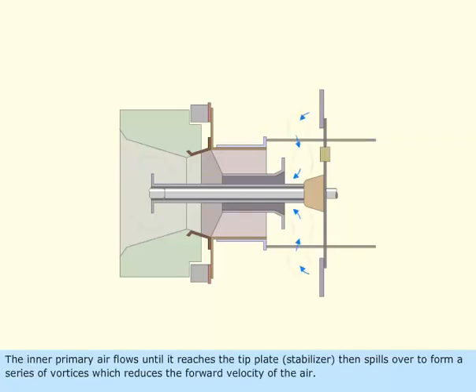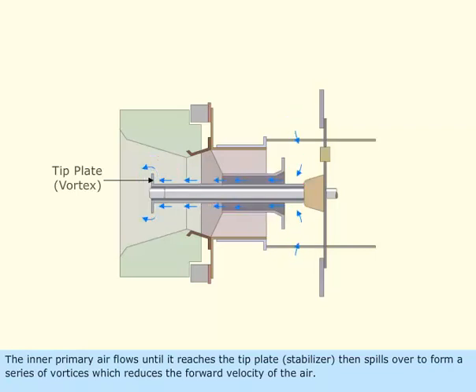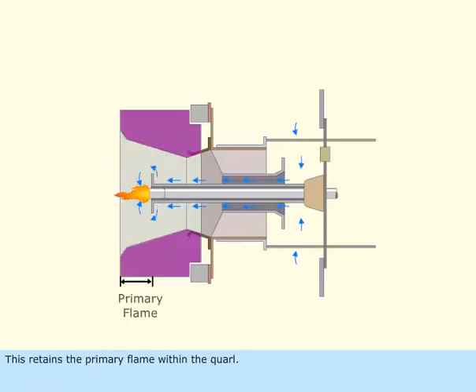The inner primary air flows until it reaches the tip plate, stabilizer, then spills over to form a series of vortices, which reduce the forward velocity of the air. This retains the primary flame within the quarl.